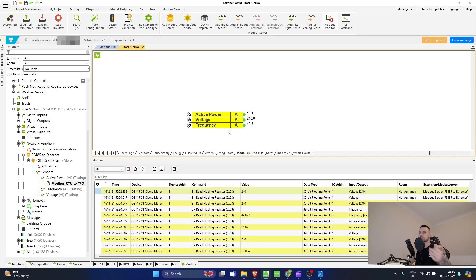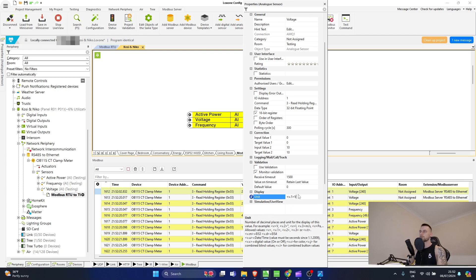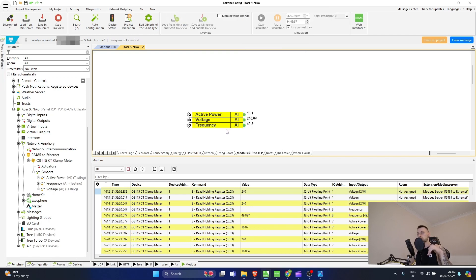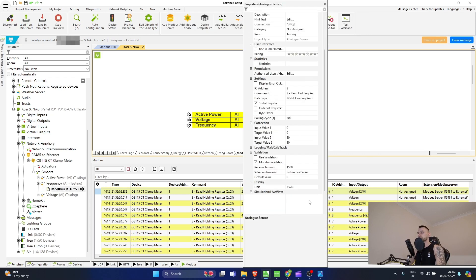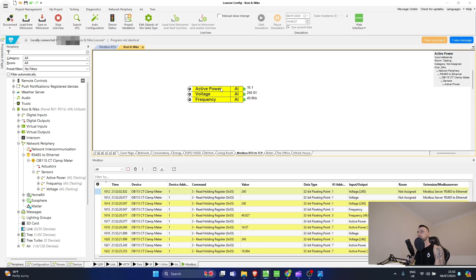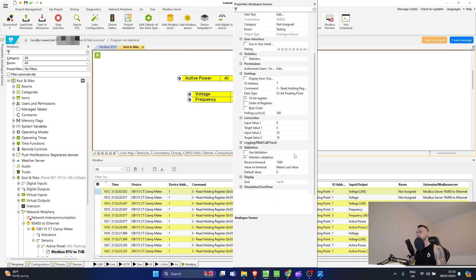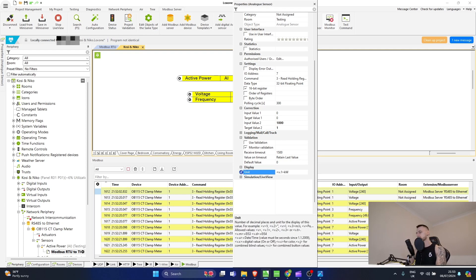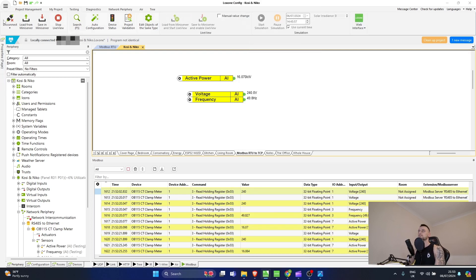From here I can do exactly the same as in the Modbus RTU video - rename things to make it look prettier and use all the same addresses but offset by one. For example, right now I can see active power is 16 watts. I can apply an offset of divide by 1000 to display it in kilowatts, and set it to three decimal places - V.3 format.